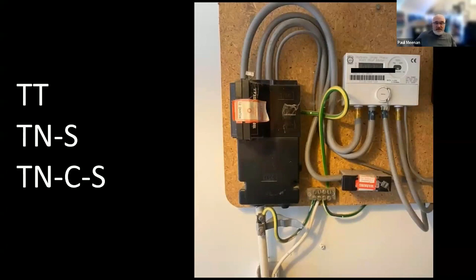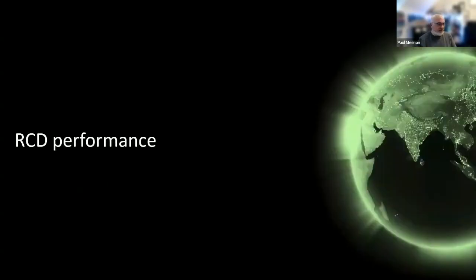We have TT, Terra, which is earth electrodes, if you only have a supply live and neutral. We have TNS, Terra neutral, separate, so it comes in completely separate. And then TNCS, Terra neutral combined separate, which is that cable there. It comes in from the bottom and basically connects into the fuse. But as you can see, that's a hybrid arrangement. In fact, if you look at the white cable in the earth terminal, that could go to an earth rod. So is it TT, TNS, or TNCS? More than likely, it's a TNCS that somebody has tried to lower the impedance by connecting to the sheath and possibly putting an electrode on, rather than fixing a network fault, because obviously, as you can imagine, networks, cables in the ground cost a lot of money to fix and repair.